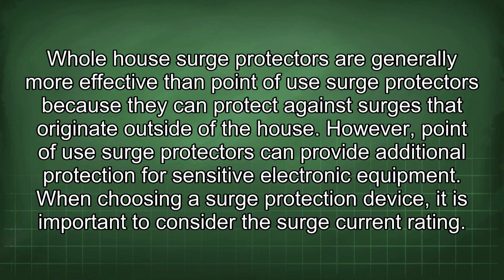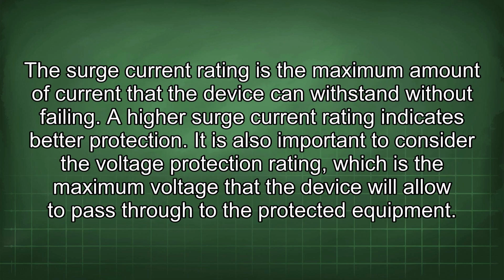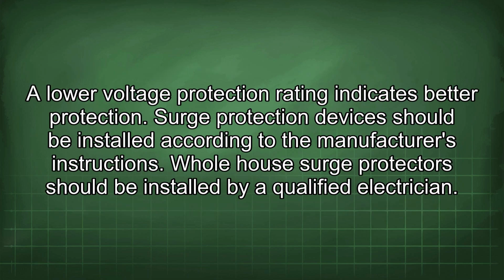When choosing a surge protection device, it is important to consider the surge current rating. The surge current rating is the maximum amount of current that the device can withstand without failing. A higher surge current rating indicates better protection. It is also important to consider the voltage protection rating, which is the maximum voltage that the device will allow to pass through to the protected equipment. A low voltage protection rating indicates better protection.